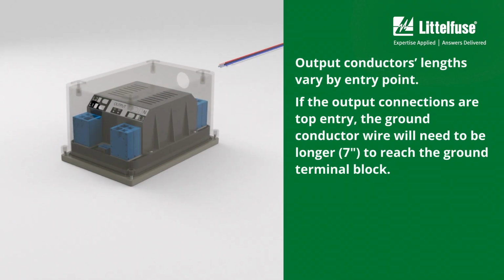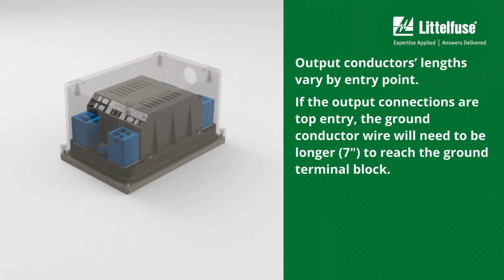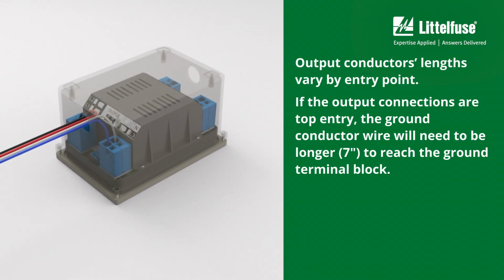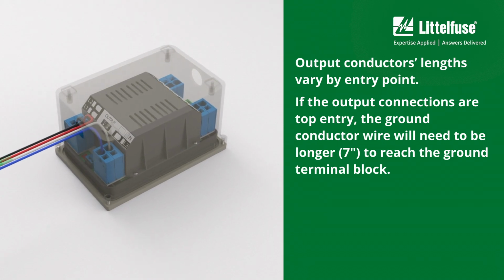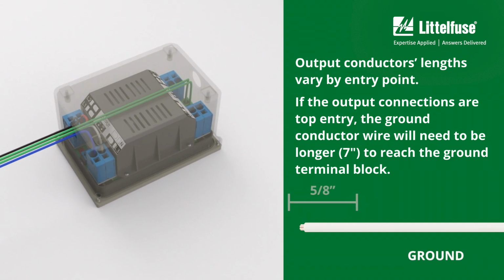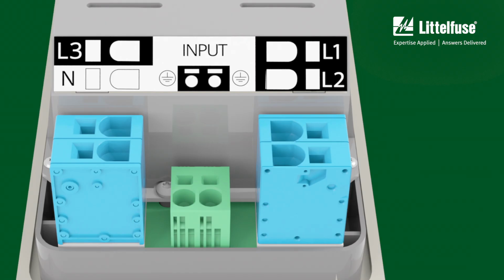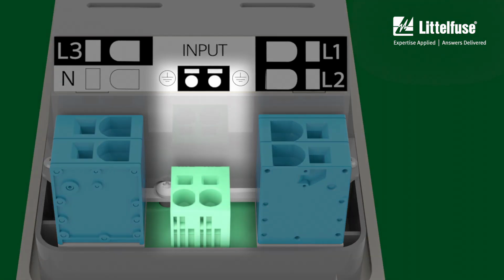Output conductors' lengths vary by entry point. If the output connections are top entry, the ground conductor wire will need to be longer to reach the ground terminal block. Strip ground conductors to 5/8 of an inch. Connect both supply and load grounds to the chassis bonding point.